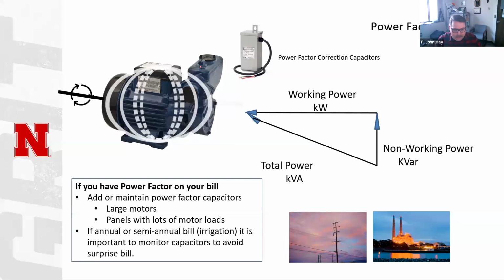Many irrigation customers pay annual or semi-annual bills. This is a little bit of an interesting situation for power factor because if the capacitors fail in mid-season, we may not know it, and thus we get this bill with a bad power factor, even though we corrected for it. So we want to be watching for that and maybe challenging our utilities: we proved that our power factor was good, we didn't have any way to identify that in mid-season. So how do we work with our utility to remedy that situation?